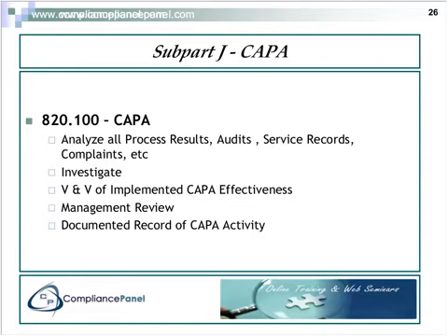So this is something that is part of the standard quality system investigation technique that the FDA does. One of the things they're going to look at almost 100% of the time is your CAPA system. So this is something that really needs to be well documented and have a closed loop system, so that you know that the CAPAs have been properly and effectively implemented.